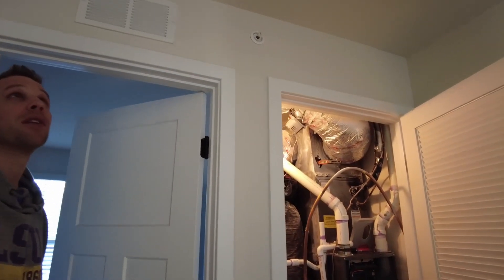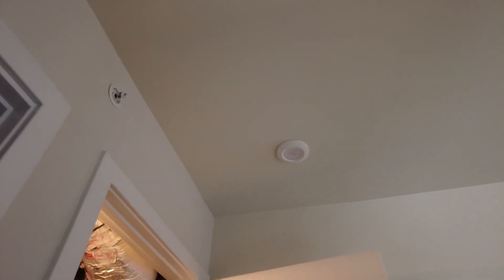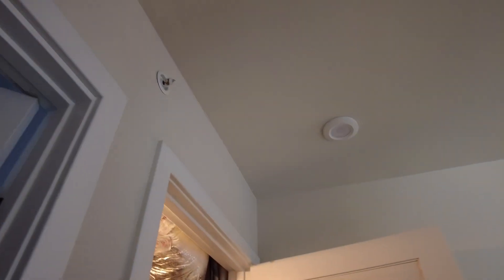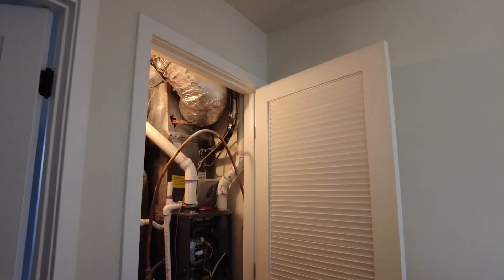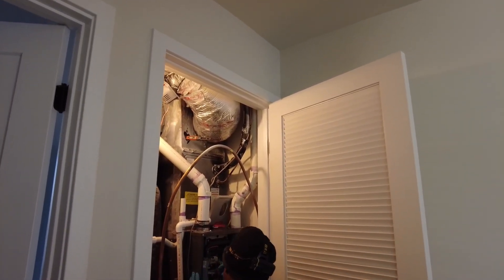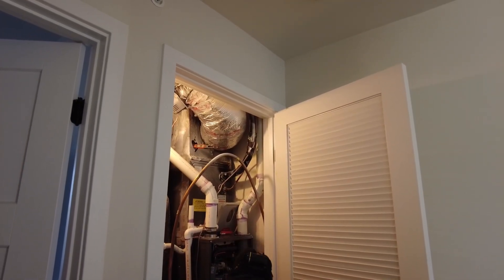This one's pretty dark, that's how I know I need a new one — I have one coming tomorrow. The second floor runs off this furnace. If that filter was really bad, it could have just gone out on high limit. This one is bad but not terrible — you can still see through it. The other one was worse. So you could have potentially had an issue with high limit. If it hits high limit, how do you reset it? I just flipped the power switch. That should have done it. Honestly, I think I did that before I changed the filter, so my sequence was off — it might have faulted out again.